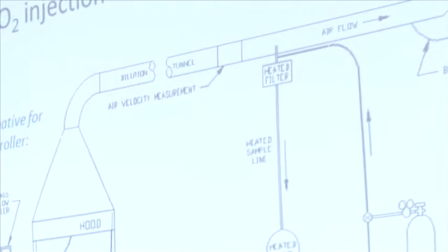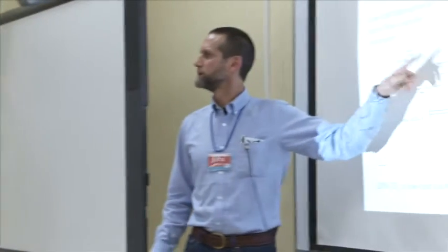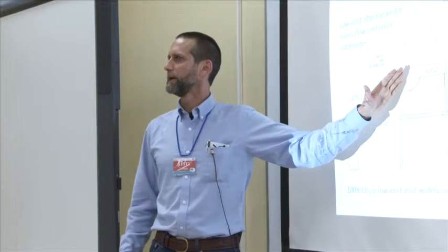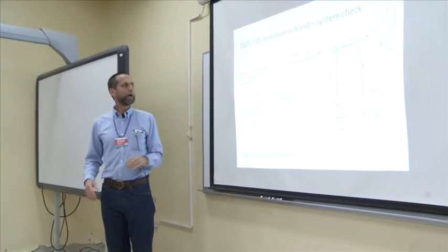That was the problem. The heated filter was leaking, and we didn't think that that could cause a problem. That was probably the most exciting day in the lab, when we finally discovered that that was what the problem was. And we never would have found it if we hadn't looked at the carbon balance, and if we hadn't used this method to chase the problem down, okay? So we would never have known that that was the problem.